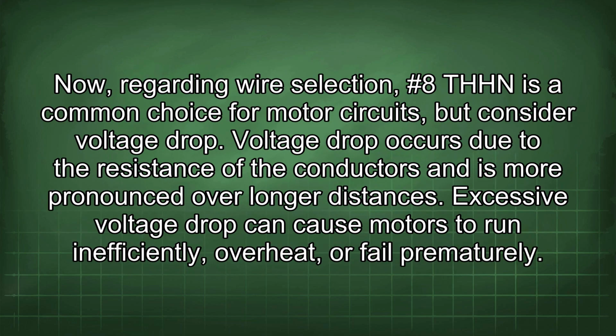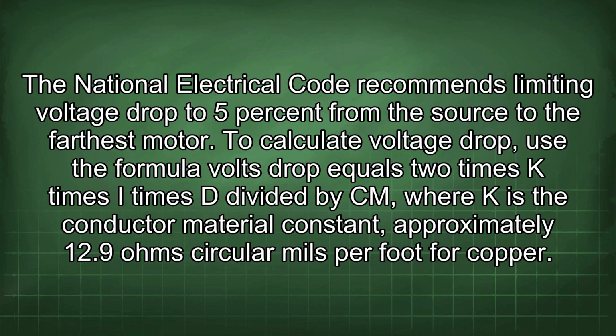Now regarding wire selection, #8 THHN is a common choice for motor circuits, but consider voltage drop. Voltage drop occurs due to the resistance of the conductors and is more pronounced over longer distances. Excessive voltage drop can cause motors to run inefficiently, overheat, or fail prematurely. The National Electrical Code recommends limiting voltage drop to 5% from the source to the farthest motor. To calculate voltage drop, use the formula: volts drop equals 2 times K times I times D divided by CM, where K is the conductor material constant, approximately 12.9 ohm-circular mils per foot for copper.